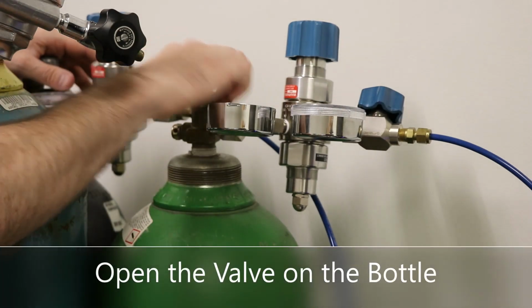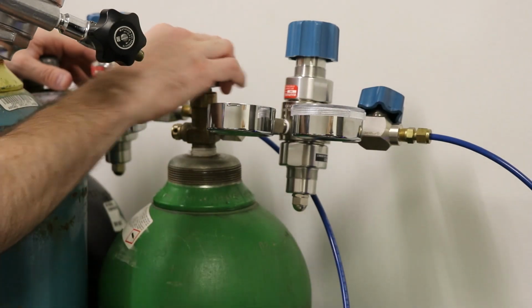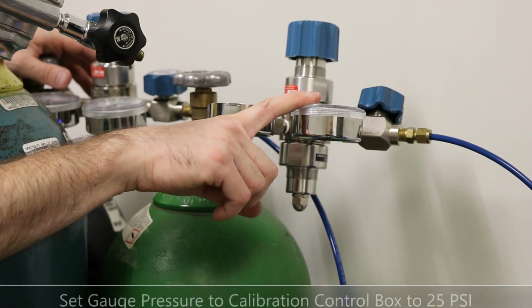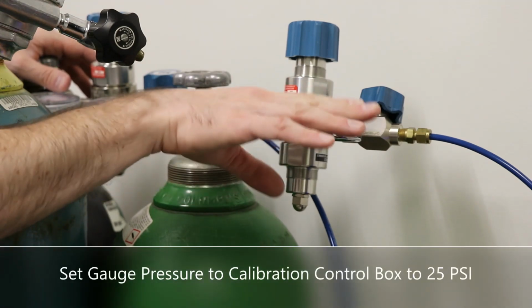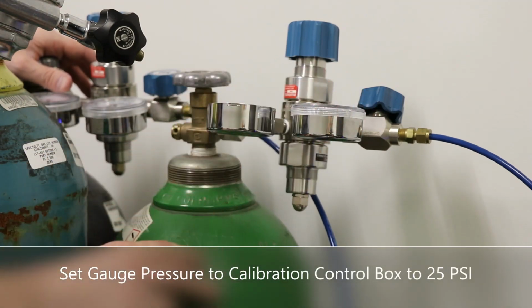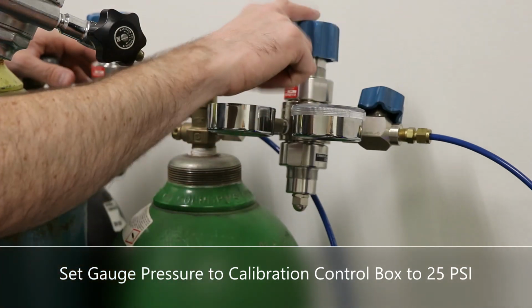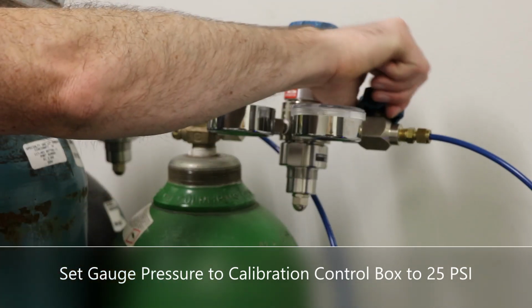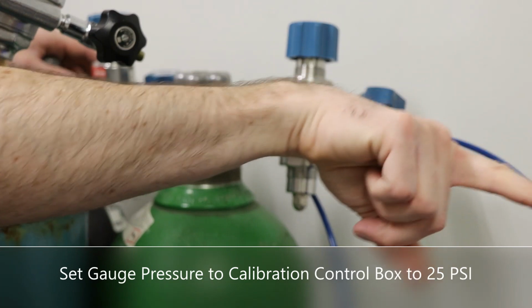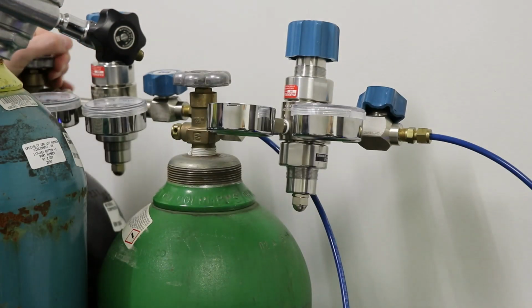Open the valve. Set these to about 25 psi for the output pressure. No more than that or it will damage the flow controllers. That can be set here. And then open this valve here to let gas flow into the system. Open nitrogen as well.